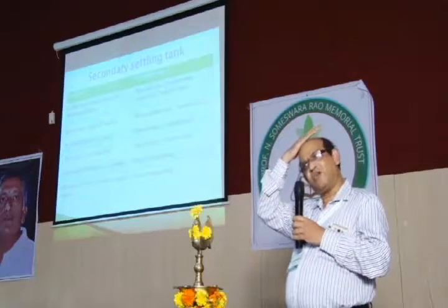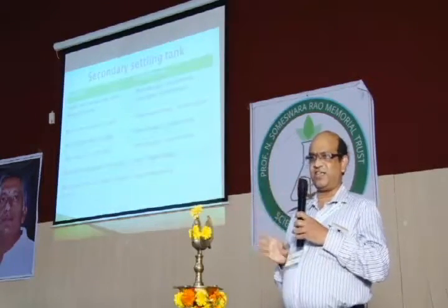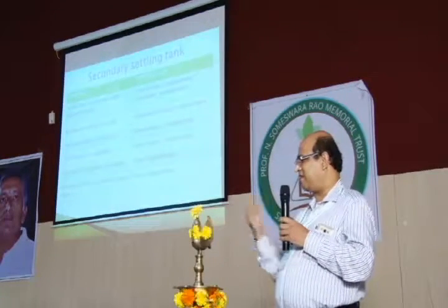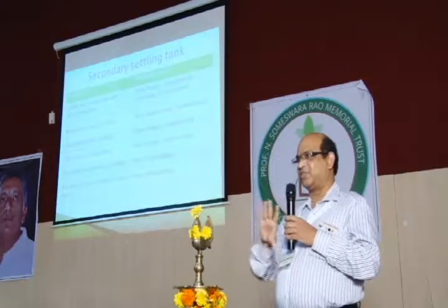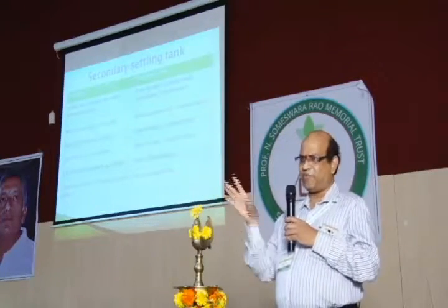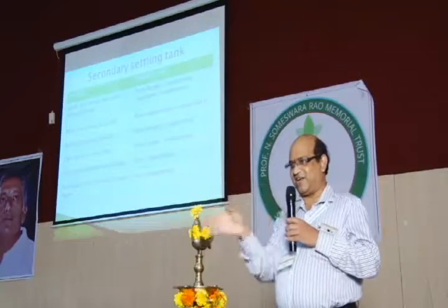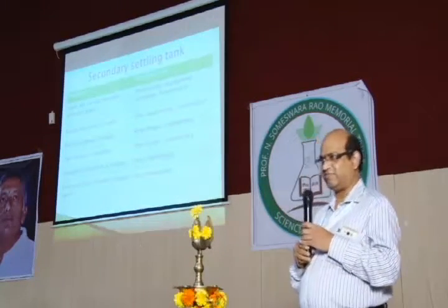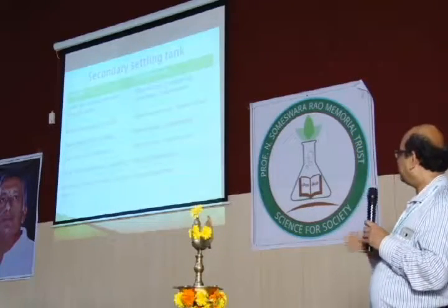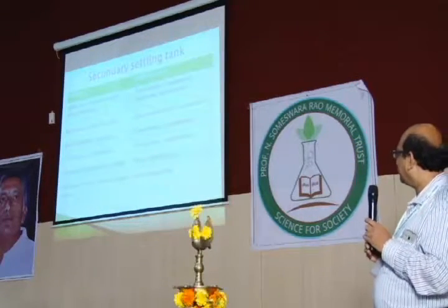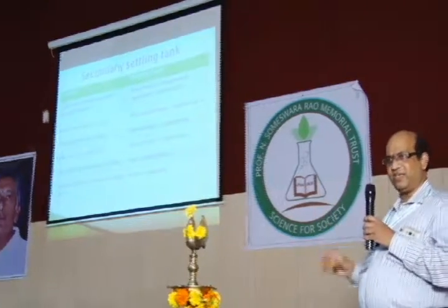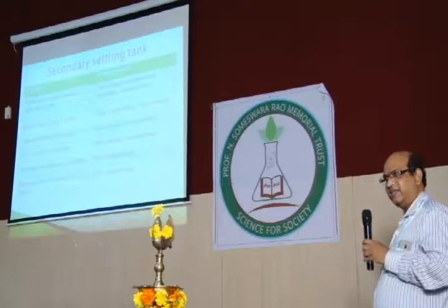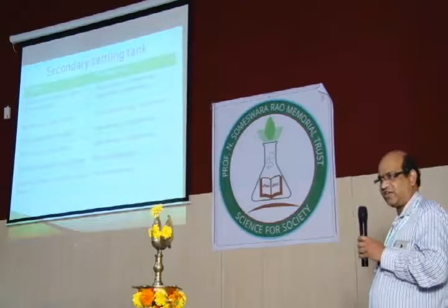In one of the paper mills we have seen, the design was excellent, done by a reputed firm. But what happens is all the BOD is well within the limit of 10 or 15, but suspended solids are still coming out. The secondary clarifier outlet is always not 100, it is around 150 or 200. Maybe some design values were not properly taken. Sometimes there is a mushroom cloud of solids, poor settlement of solids. All this is mainly poor design. The secondary clarifier should be properly designed to remove the sludge and to separate the return sludge.